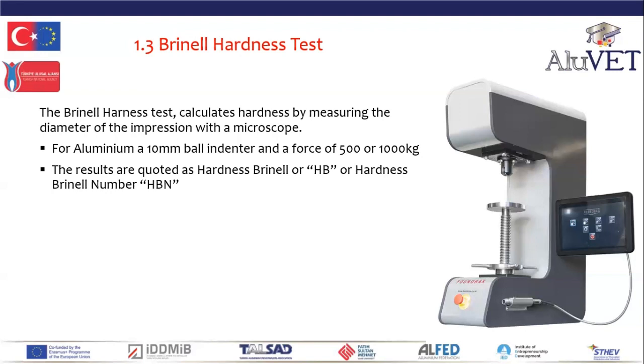And the method that we carry out a Brinell hardness test is that we place the sample on the platen, bring the platen up to the ball indenter, so the ball indenter just touches the surface, and we then apply the indentation load, take the load off, and then measure the diameter of the resultant spherical impression using a scaled microscope.